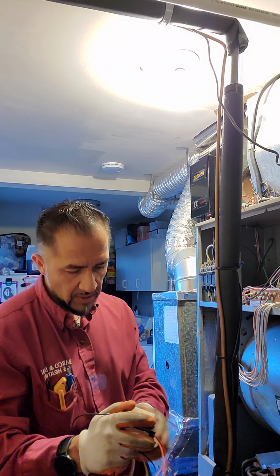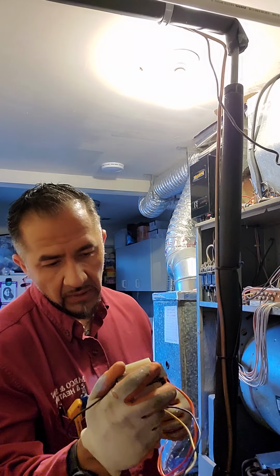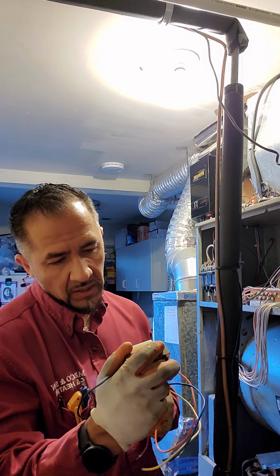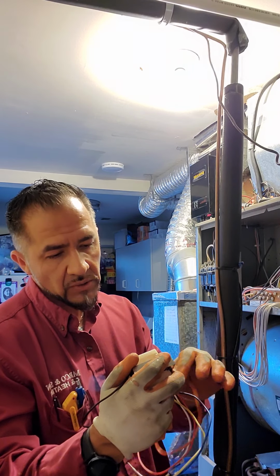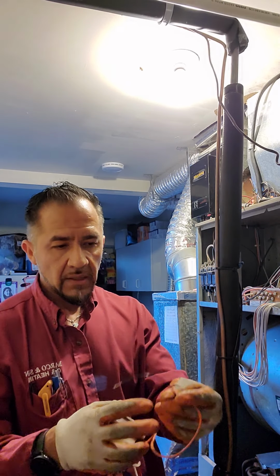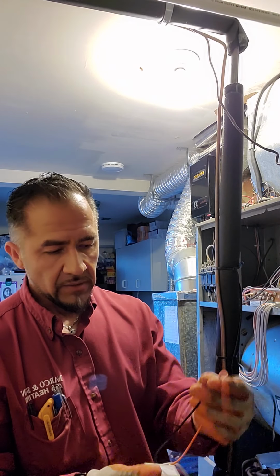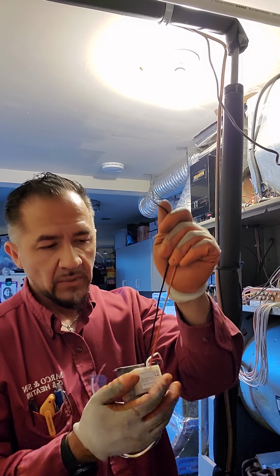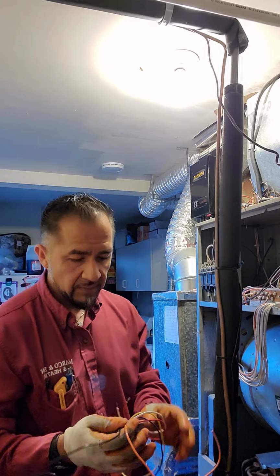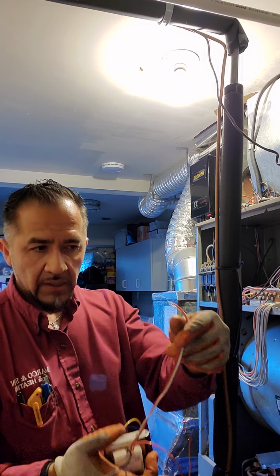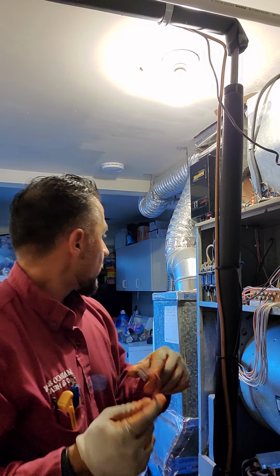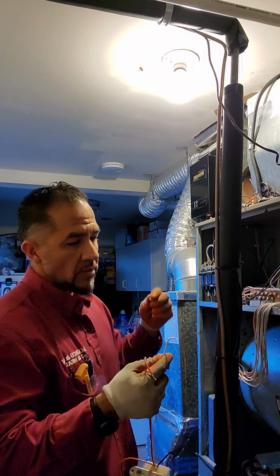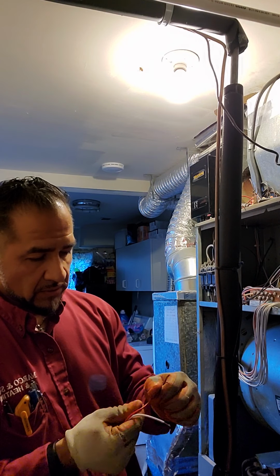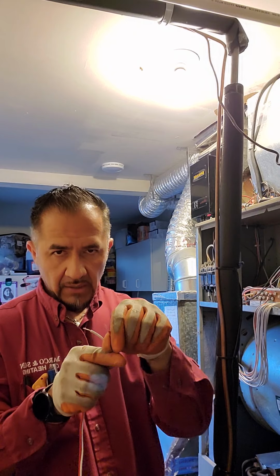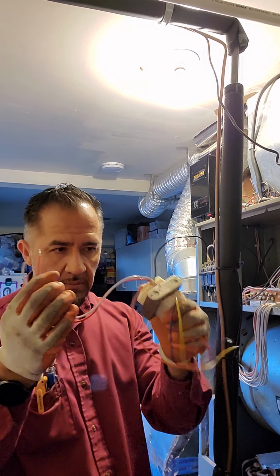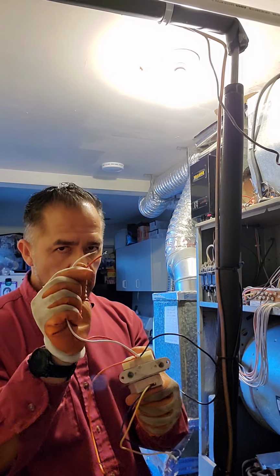We don't need that on this one because we need 240. Red is 208, and orange is 240. So we're going to need the black and the orange for the 240 volt circuit, because remember the Z100 is 240 volts. So these two right here are not going to be in use. The ones that we're not using, we need to make sure are not connected to each other, because there's voltage in every single wire, even though they're not in use.